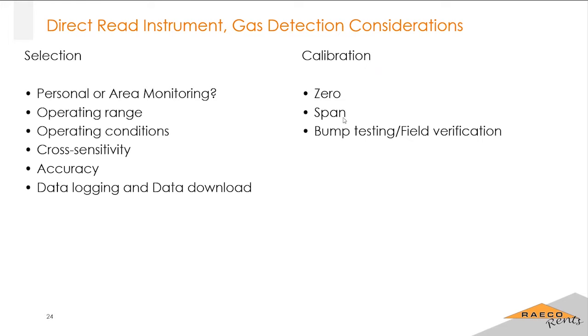And of course, your calibration. If you were to rent equipment, we calibrate this equipment right before we send it out, so everything's going to come freshly calibrated. But if you own your equipment and you're in the field using it, definitely make sure that you at least do a zero calibration and a span calibration. The time periods on that are very up in the air with most people. Any manufacturer is going to recommend that you bump test daily. A bump test is really just running gas over a sensor to ensure that it's responding to the gas properly. That makes sure that it's responding, but not necessarily that it's responding with the correct concentration. So my recommendation is to do a zero calibration and a span calibration at minimum once a month. I would recommend it more often as a best practice, but at minimum once a month on these.